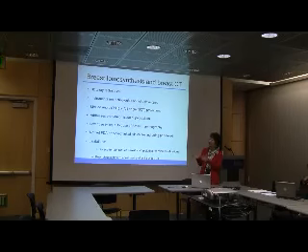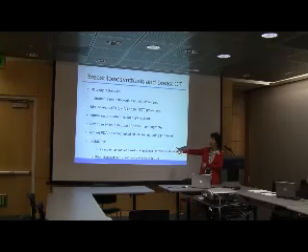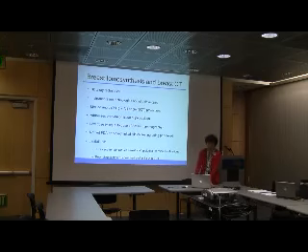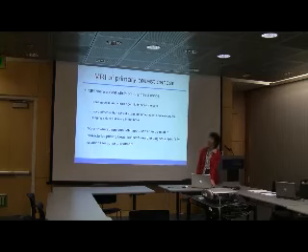And they suffer from a few problems that engineers are trying to address right now, and we may see them come to fruition. But for one, in the tomosynthesis systems, they found that there could be reduced sensitivity to calcification, so it's not quite performing at the level of digital mammo. Also with the CT approaches, it's difficult to build that instrumentation so that you can see the chest wall and axilla very clearly.